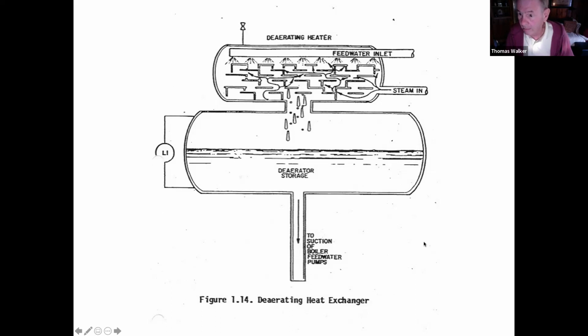Most DAs only operate at about 10 PSI. Most boilers operate at 100 PSI. What's easier to do? Pump chemicals into something at 10 pounds or 100 pounds? You get the idea. And any chemicals that I add to this water, where are they going to end up anyway? In the boiler, right?